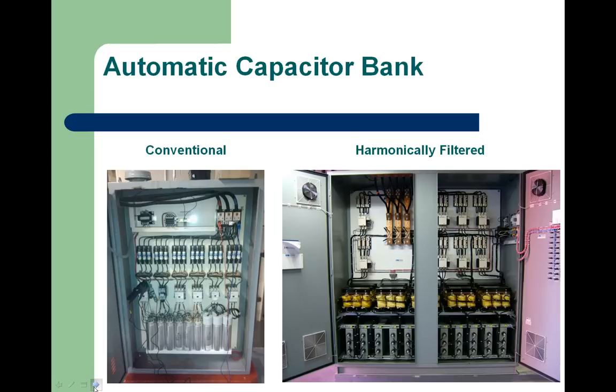Here's a couple of good-looking capacitor banks. These are both automatic capacitor banks, and as we'll get to a little later, this is a conventional capacitor bank on the left. We have our fuses, we have some inrush current limiters, we have the contactors and the individual capacitor cells. So this particular bank will step in and out as required to maintain whatever target power factor that one is set for. The one on the right here is a harmonically filtered capacitor bank, which is becoming more and more of a requirement these days, with more harmonic loads being added to plants, such as AC variable frequency drives. It's probably one of the largest contributors of harmonics nowadays. DC drives, of course, have very high harmonics, as well as rectifiers.